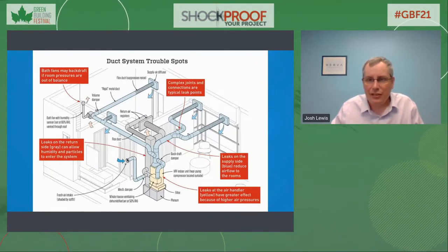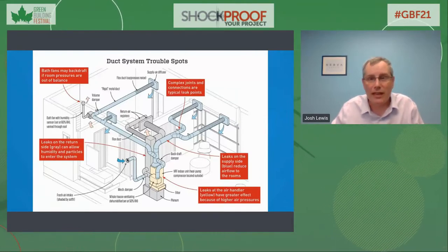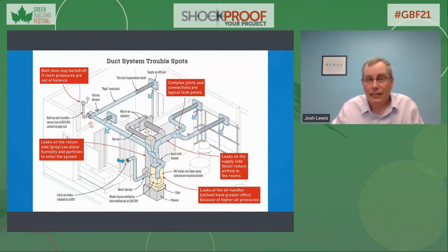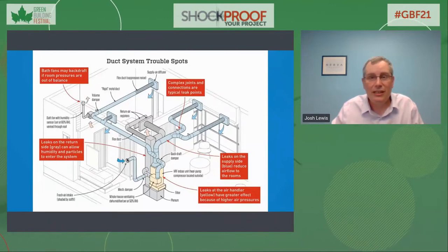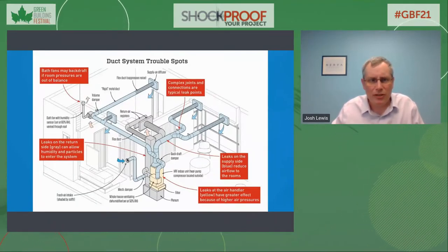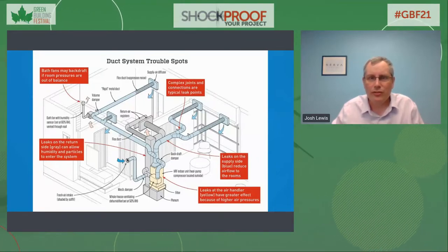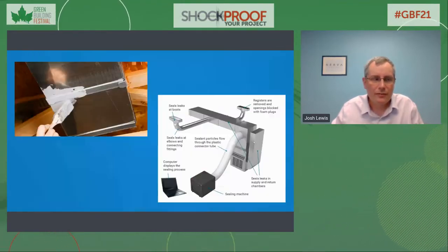So why is there so much leakage? Well, the traditional methods of sealing ductwork from the outside with mastic tape and caulking are not perfect. Oftentimes, sealing is missed on hard-to-reach areas or lengthwise seams that seem to have very little leakage in a small section, but cumulatively add up to a significant amount of leakage over hundreds of linear feet of ductwork.